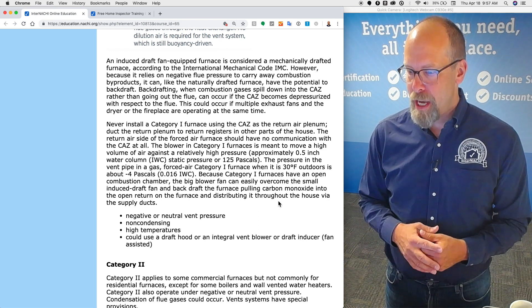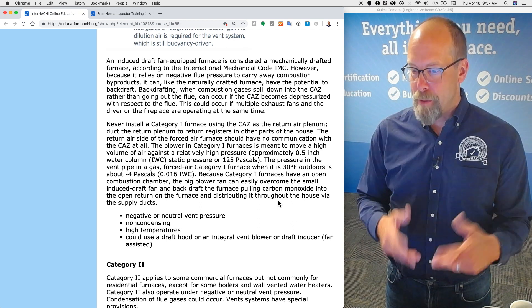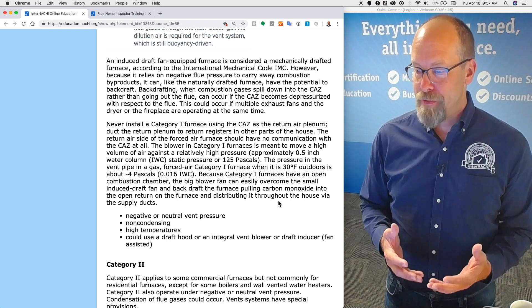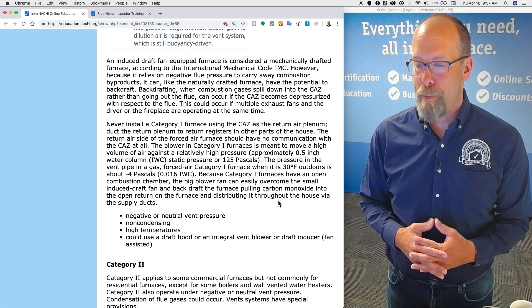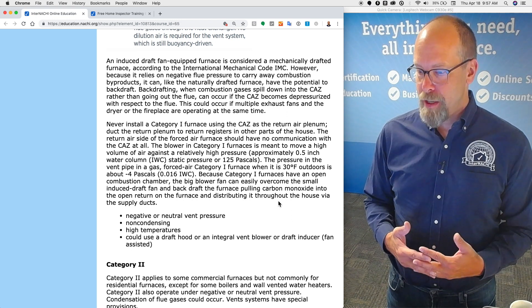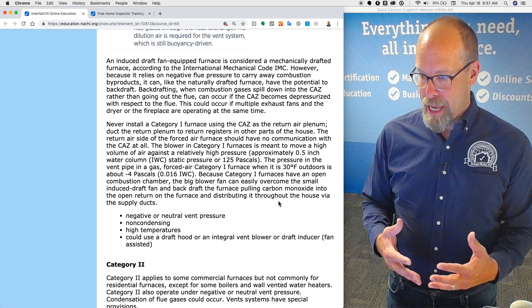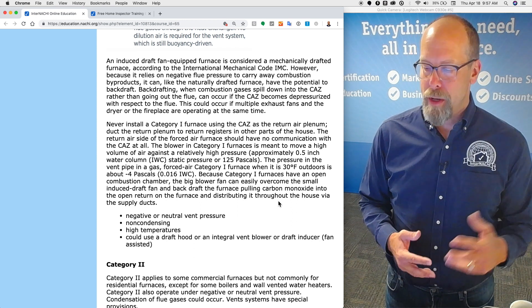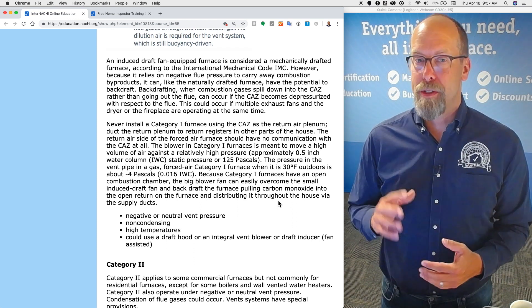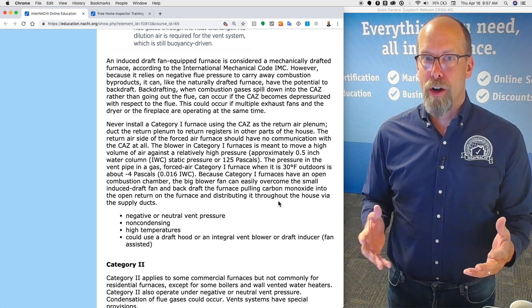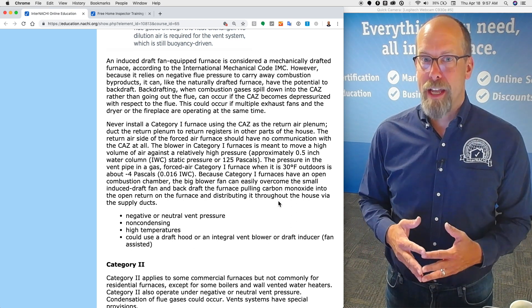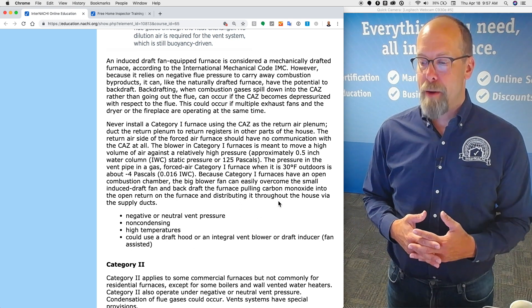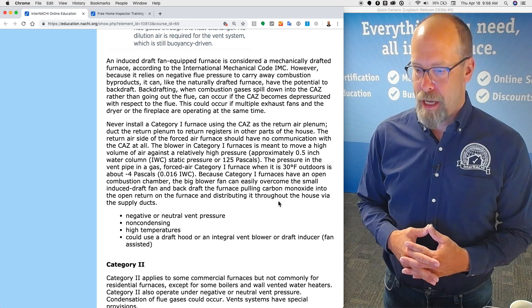However, because it relies on negative flue pressure to carry away combustion products, it can, like the naturally drafted furnace, have the potential to backdraft. Backdrafting, when combustion gases spill down into the CAZ rather than going out the flue, can occur if the CAZ becomes depressurized with respect to the flue. This could occur if multiple exhaust fans and the dryer, the clothes dryer, or the fireplace are all operating at the same time.